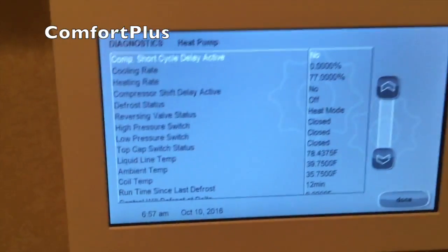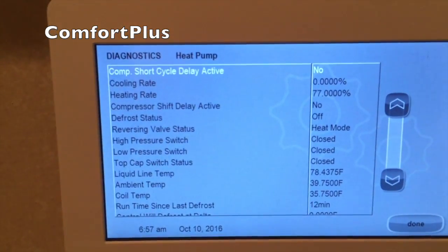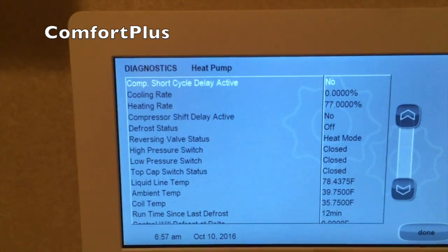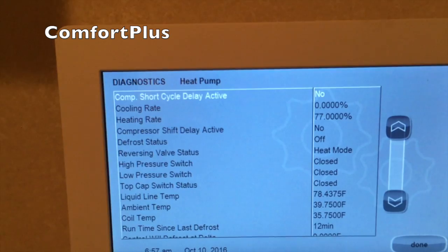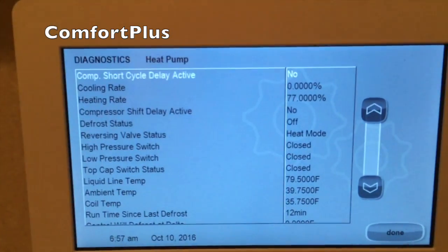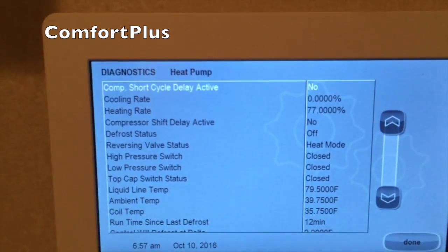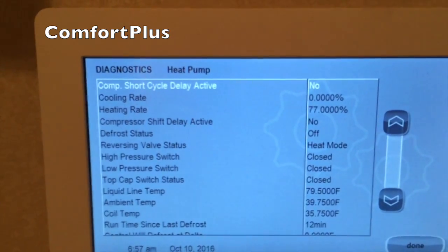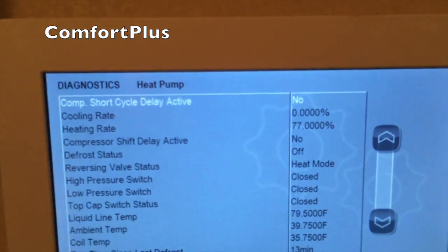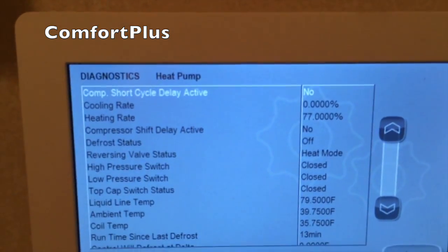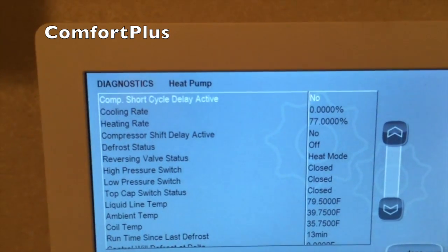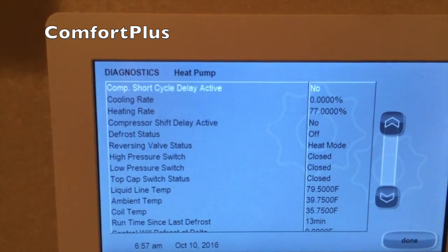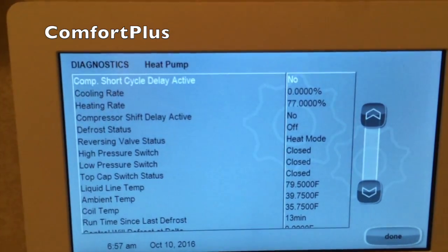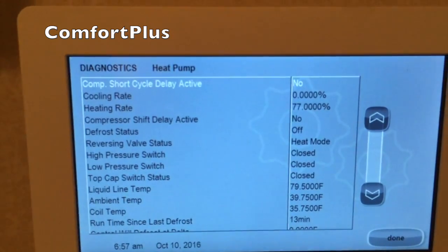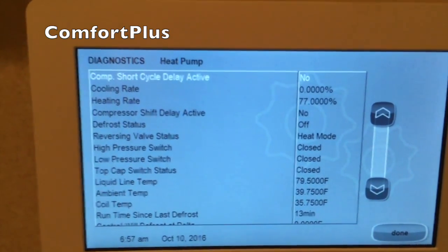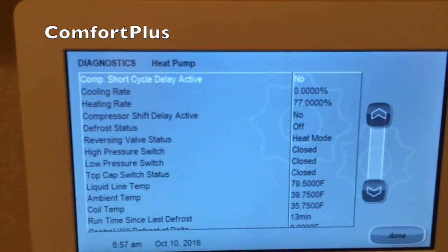What's significant about that is I'm only heating one zone right now. And that one zone is only using like 700 CFM of air from the air handler. So we have, I guess, 44% of the 4-ton unit inside. And right now we have 77% of a 4-ton unit outside, which means I'm getting a lot warmer discharge temperature than I would have gotten out of the old 2-ton heat pump. Had it been on here right now, I would have been getting 100% indoors and out. But 100% of a 2-ton is less than 77% of a 4-ton.